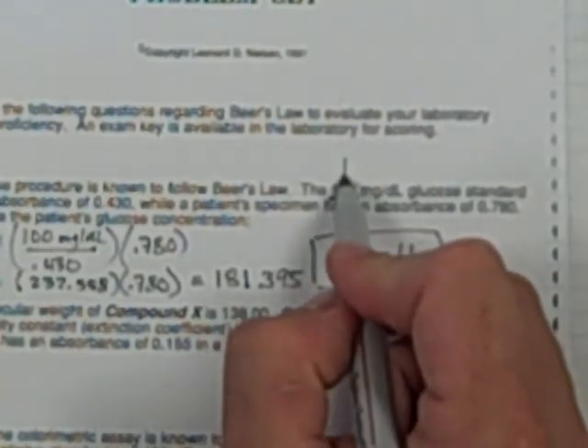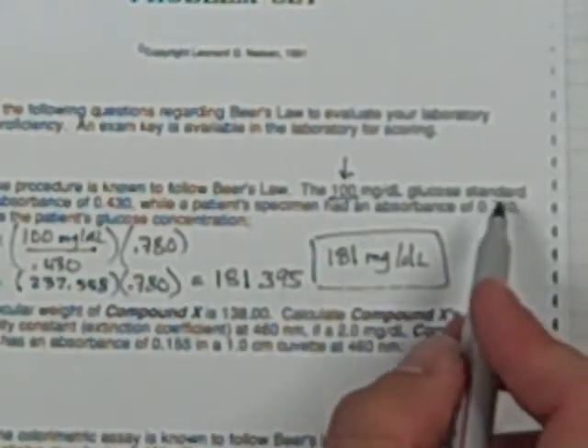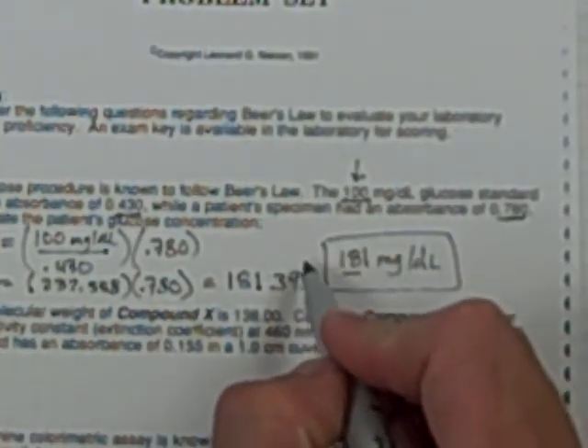And you can do a quick check and say, hey, if 100 milligram per deciliter standard had an absorbance of about 0.430, 0.780 is almost double that. So I look, 181 is almost double 100. It's a quick check to make sure that there isn't something terribly wrong with my math. If I had gotten something like 18 or 1800, I'd have a good idea that I had made some sort of mistake.